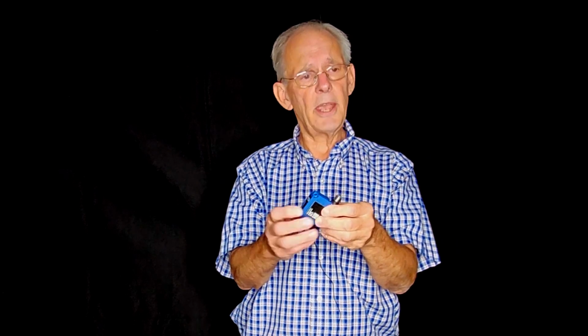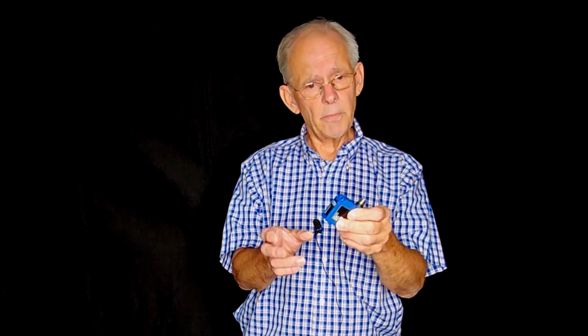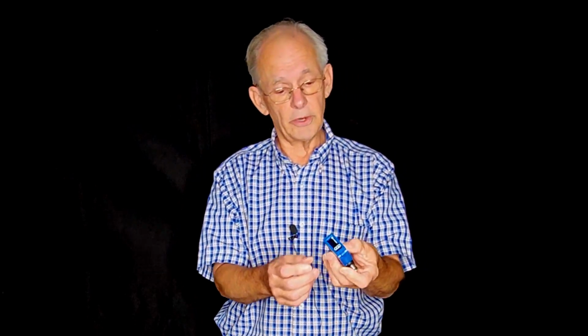I can get the same style, same case and all, in ones that will measure down to 10 or 15 microns of accuracy. So you can measure the thickness of a piece of paper with one of these, or a thin piece of metal. So very useful. And again, it's 4 to 20 milliamps output, puts out the same signal as all the other devices that we're showing you. So these are quite expensive right now.